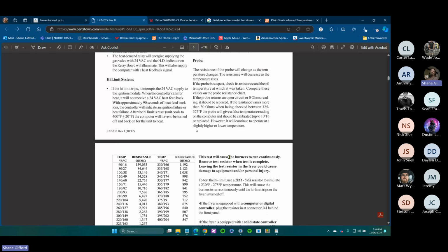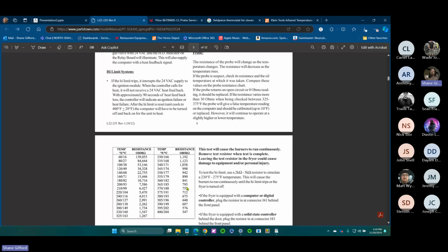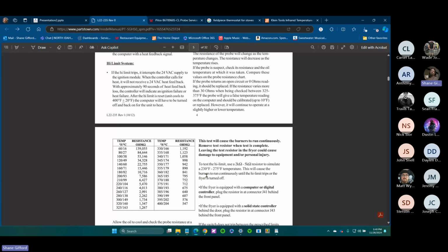High limits that are reading over, meaning reading a much lower resistance, but we know that the vat is low. So you would see something like this if the customer says, oh, my oil fryer's not working, I turn it on, it runs for a minute, and then it shuts off. Well, that could be a couple of different things causing it to shut off. But this is something you will always want to check, because it's cool if this thing fails low, meaning it's actually like 100 degrees and it trips because it thinks it's 450, 500 degrees. That's the best possible scenario for that high limit to fail.